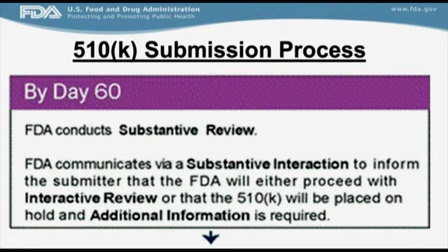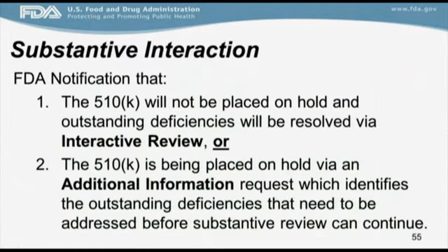By day 60, the FDA will communicate with you as to whether or not your 510K is going to proceed through interactive review or they will make an additional information request. So a substantive interaction they will have with you by day 60 can be that your 510K will not be placed on hold and the outstanding deficiencies will be resolved via interactive review, or that your 510K will be placed on hold and you will receive a formal additional information request which identifies the outstanding deficiencies that need to be addressed. So let's go into those specifically.